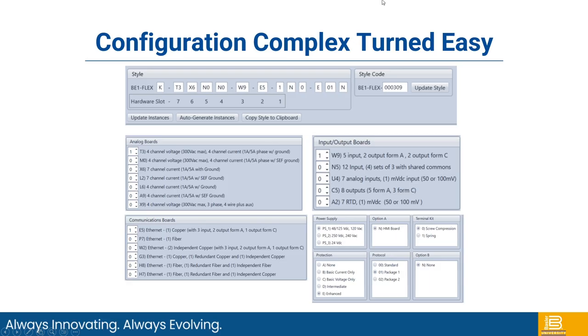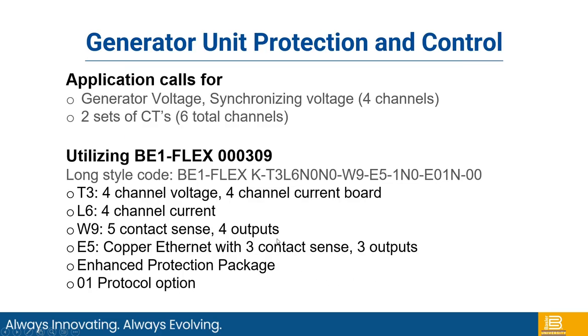So again, you go through the configuration tool and the style selection. For this application, again, we need the T3, which is the 4-channel voltage and 4-channel current. We need a L6, which is 4 additional currents, so you have a total of 8. Communication board, E5 with 3 inputs, 3 outputs. The W9 and your power supply 1 again. You're enhanced because you're doing differential, and protocol package, just assuming no IEC 61850, including Modbus and DNP3. So here's your style and your options.